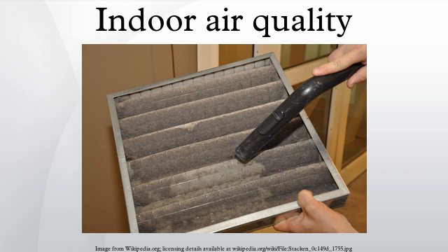In Hong Kong, the EPD established indoor air quality objectives for office buildings and public places in which a carbon dioxide level below 1000 ppm is considered to be good. European standards limit carbon dioxide to 3500 ppm. OSHA limits carbon dioxide concentration in the workplace to 5000 ppm for prolonged periods, and 35,000 ppm for 15 minutes.